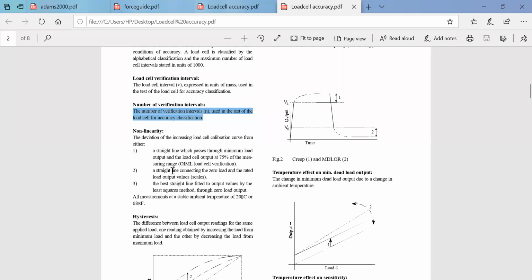The second one is a straight line connecting the zero load and the rated load output, where the values keep on varying. So how was the condition of the graph at zero load, and how does the graph increase when you add the load? If it is increasing abruptly, meaning for small values it is showing a larger deviation, and again for increased load it is showing a smaller deviation, it is not varying linearly, it is changing in a non-linear way, right? So this is the nature of a non-linear variation for the deviation of the errors. So this is the second option.